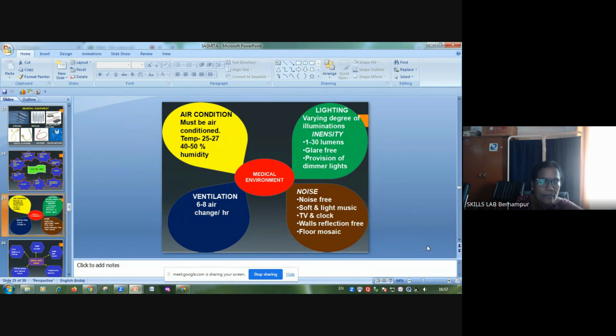These are the plans for designing the medical environment: ventilation 6 to 8 air changes per hour, noise-free, soft light, music, TV, clock, walls reflection-free, floor mosaic, lighting with varying illumination intensity of 1 to 30 lumens, glare-free with dimmer lights, and air conditioning with temperature 25 to 27 degrees and 40 to 50% humidity — all must be included in the medical environment.